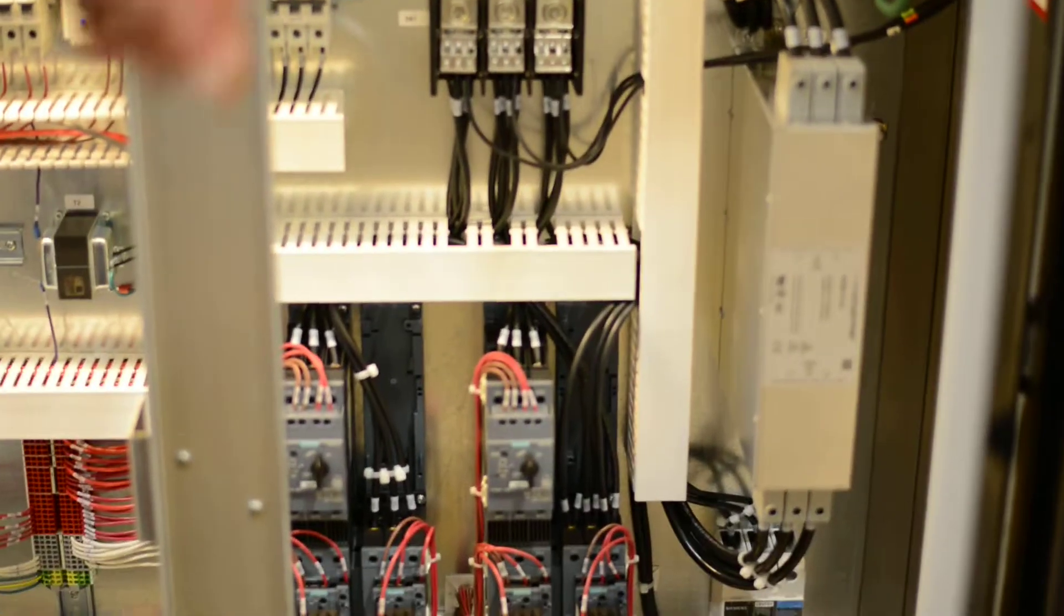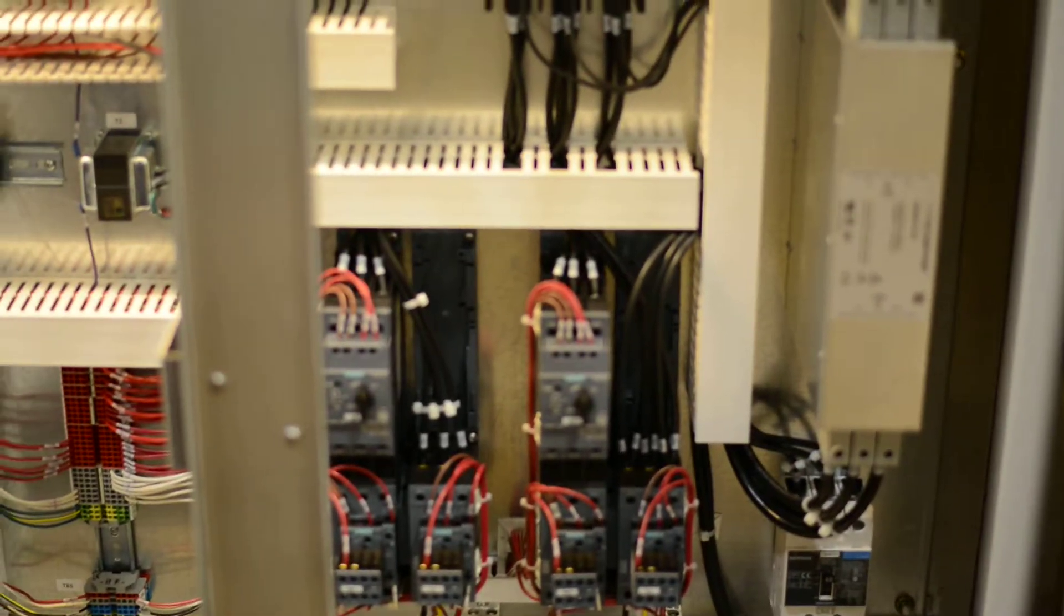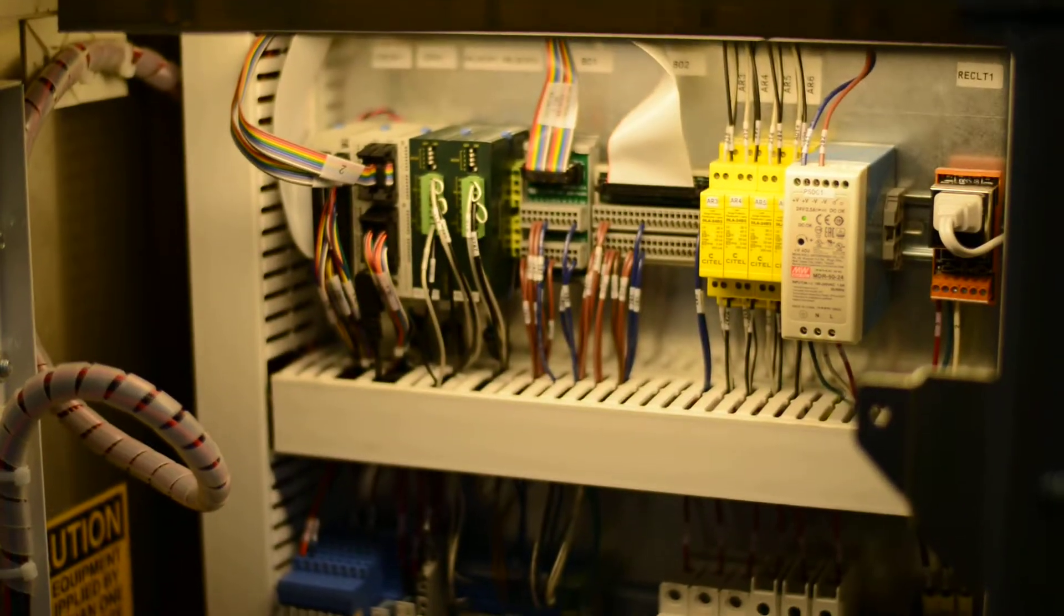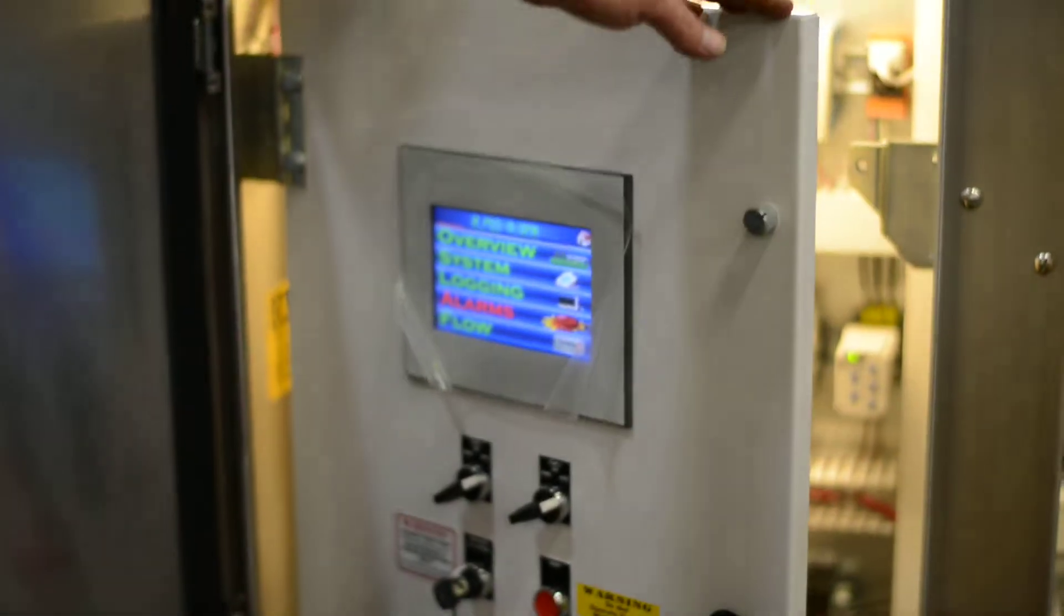Check your motor leads, wires to the contactors, and into the filters. Check your connections over here and just give them a slight tug. If nothing comes apart, you're good. If it does and you need the wire diagram to relocate that, you should have access to it. Everything is numbered so it should go back together fine.